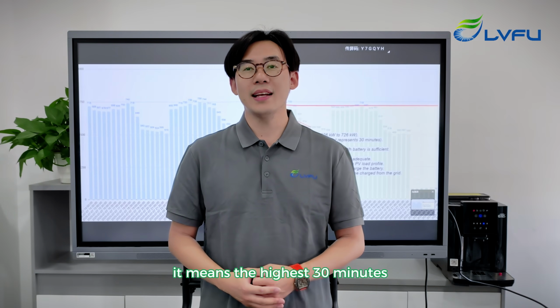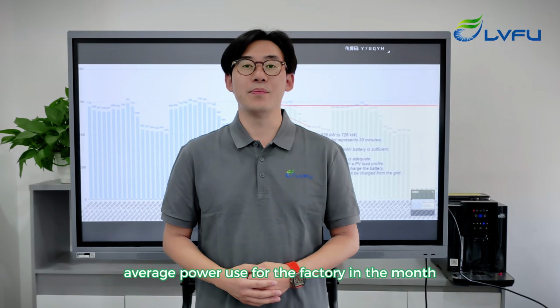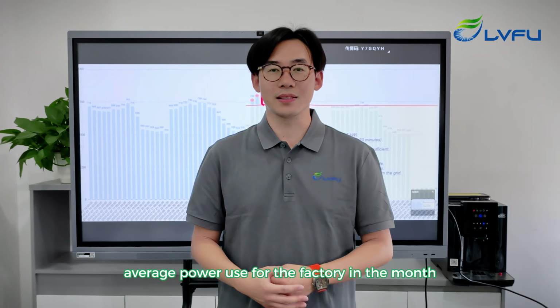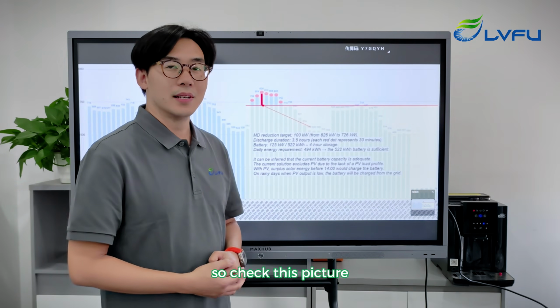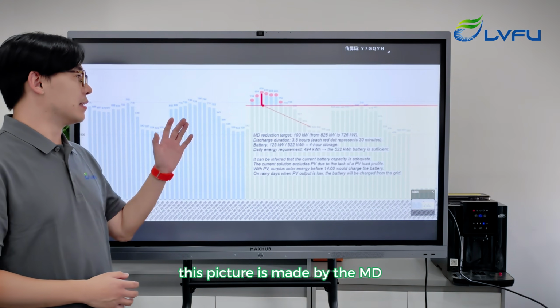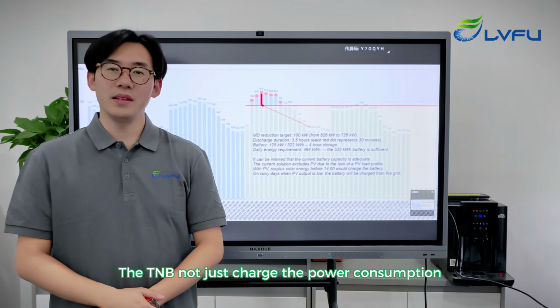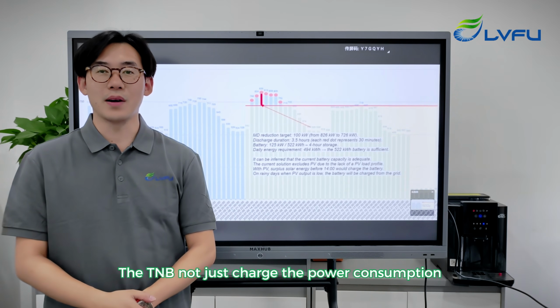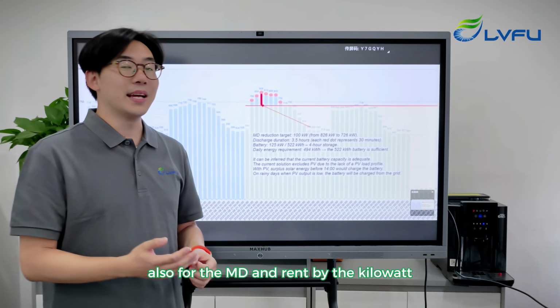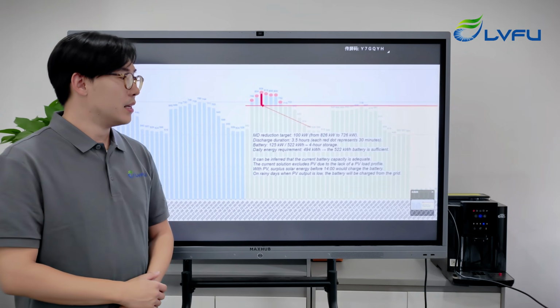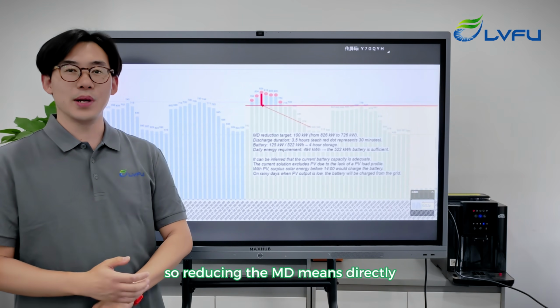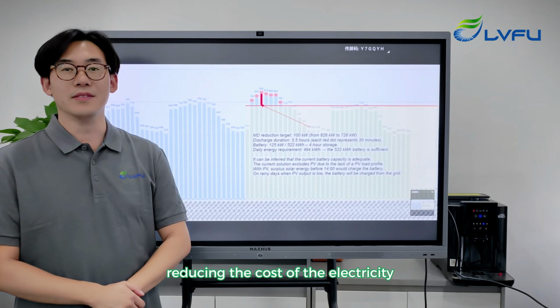The MD stands for maximum demand. It means the highest 30 minutes average power use of the factory in the month. Check this picture, which is made by the MD. TNB charges not just for the power consumption, but also for the MD, rented by the kilowatt. So reducing the MD directly reduces the cost of electricity.